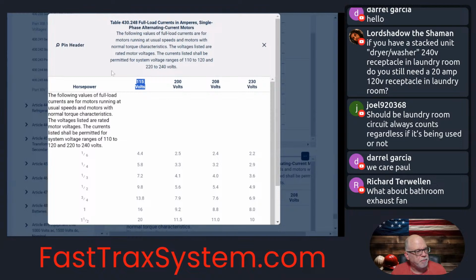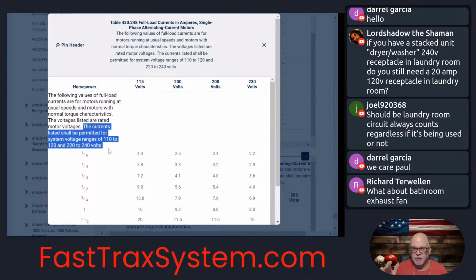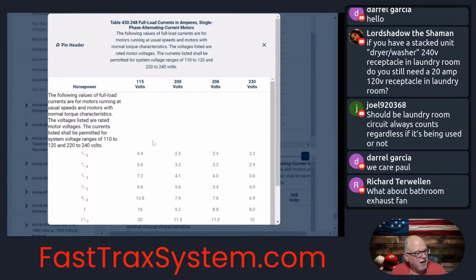And the permission for that is all right here. So in case that ever confuses you, they might say, wait a minute, the nameplate says 120, but why are we using the 115 column? Well, it should be a no-brainer because there's no 120 column. It goes without saying. So in our case here, it is 9.8 amperes. That's what we'll be working with.